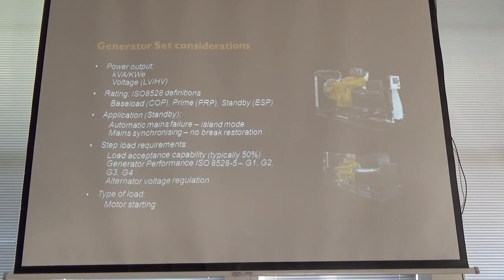So, one of the key things again, kVA, kilowatts. Funnily enough, with diesels you talk kVA, with gas sets you talk kilowatts. Don't know why, but it's just the way it is. Normally it's 0.8 power factor anyway. We do LV and HV systems. The main thing to consider is the running parameters of the unit, and that ties in with the ratings. So the ISO 8528 definitions tend to be the most important things to be aware of for the suitable selection of the unit, how long you want it to run, etc.